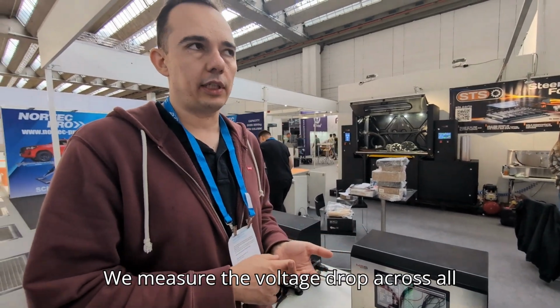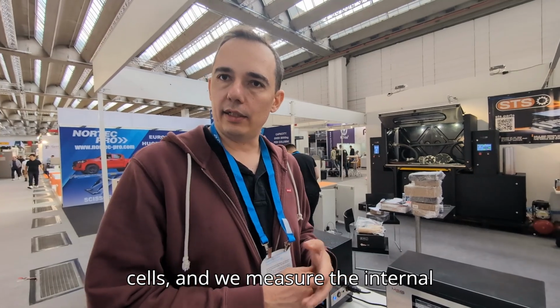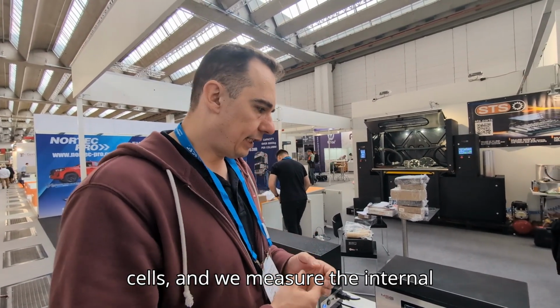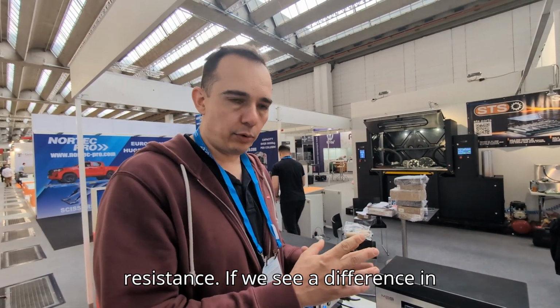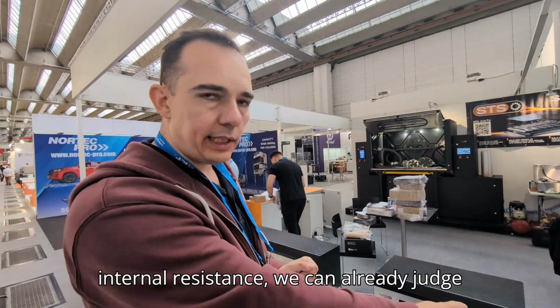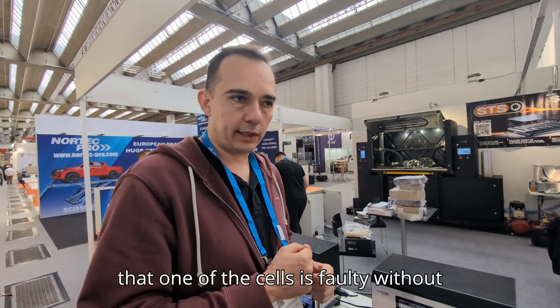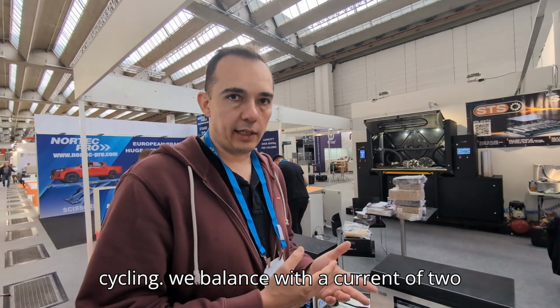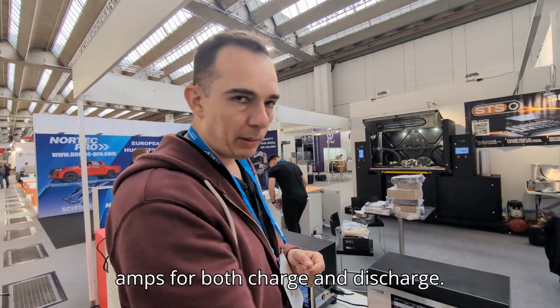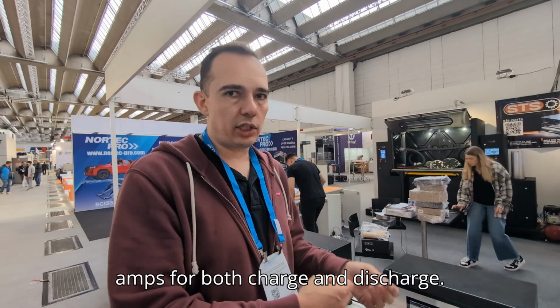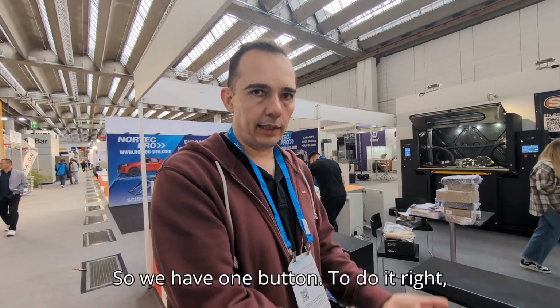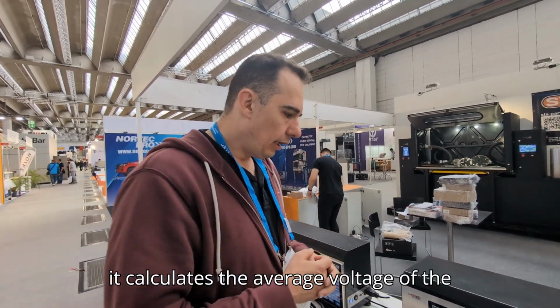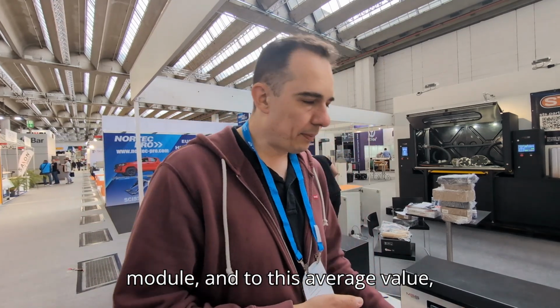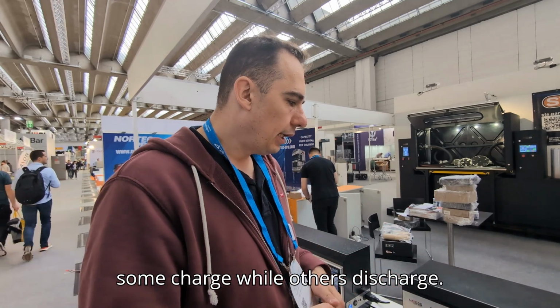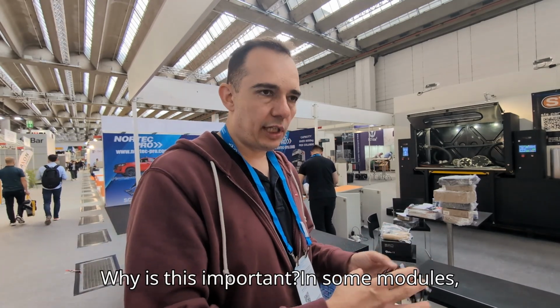We measure the voltage drop across all cells, and we measure the internal resistance. If we see a difference in internal resistance, we can already judge that one of the cells is faulty without cycling. We balance with a current of 2 amps for both charge and discharge. So we have one button. To do it right, it calculates the average voltage of the module, and to this average value, some cells charge while others discharge. Why is this important?